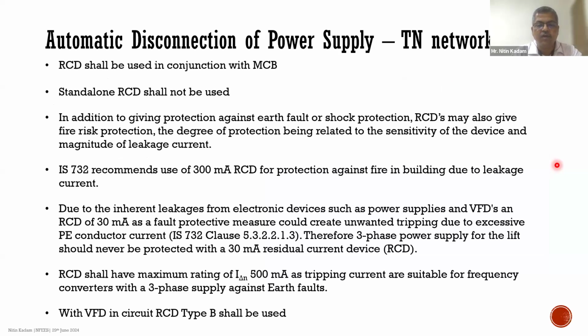Now, we have already covered this point generally, but let me touch upon the RCD requirements here. The RCD should not be used standalone. It should always be used in conjunction with, or in addition to, the MCB. Generally, IS 732 recommends use of a 300 milliamp RCD for protection against fire in the building. And RCDs up to 500 milliamps as a tripping current value are suitable for frequency converters with a 3-phase supply against earth fault.